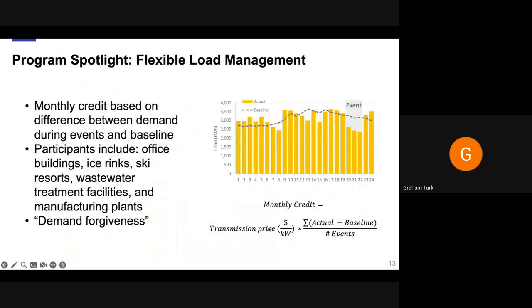When we revised the pilot we changed the compensation to pay-for-availability: as long as customers responded when we asked — defined by three-hour event windows — we'd calculate their credit for each month by the difference between their actual demand and a temperature-based baseline, similar to what wholesale markets do for demand response. We'd average that over all events in the month. This shifted risk away from customers — all they had to worry about was responding when asked — and put the risk on us to call events at the right time, sometimes splitting event calls across customer groups across different hours.